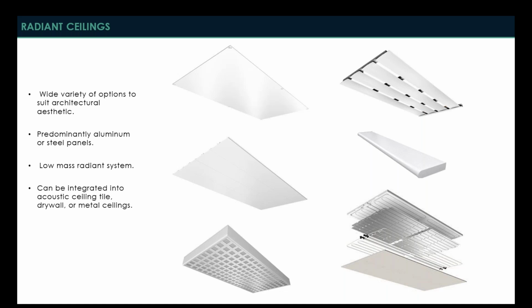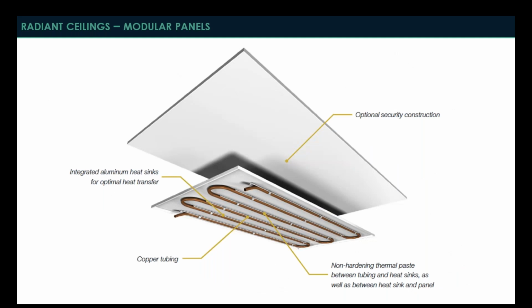And these aluminum and steel panels are what we would consider to be a low mass radiant system. And again, they can be integrated into ACT, acoustic ceiling tile ceilings, into drywall, into metal ceilings, or the radiant panels could actually become the ceilings themselves. So the first type of radiant ceiling panel I'd like to talk about is what is known as a modular panel. And I also consider the modular panel to be sort of a tray type application.